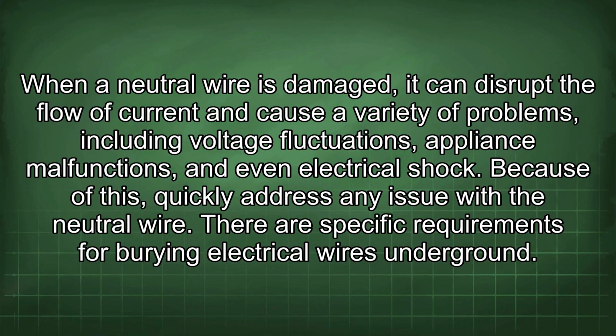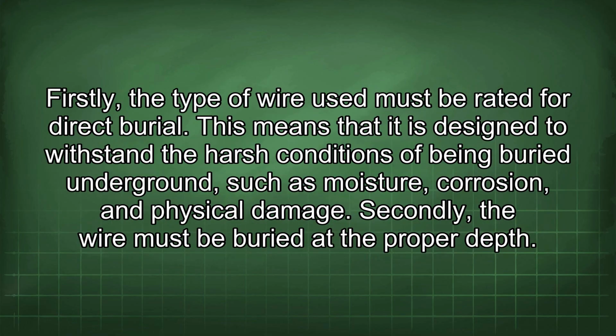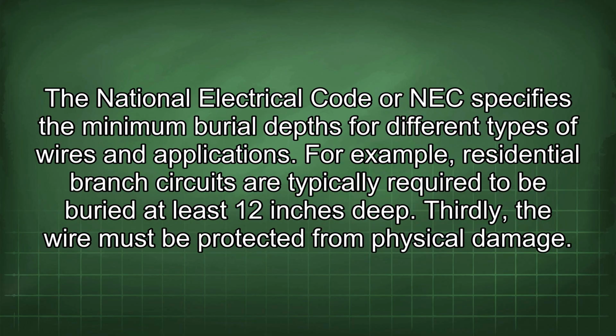There are specific requirements for burying electrical wires underground. Firstly, the type of wire used must be rated for direct burial. This means that it is designed to withstand the harsh conditions of being buried underground, such as moisture, corrosion, and physical damage. Secondly, the wire must be buried at the proper depth. The National Electrical Code, or NEC, specifies the minimum burial depths for different types of wires and applications. For example, residential branch circuits are typically required to be buried at least 12 inches deep.